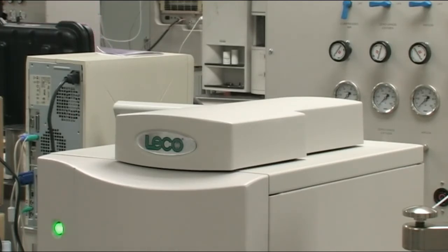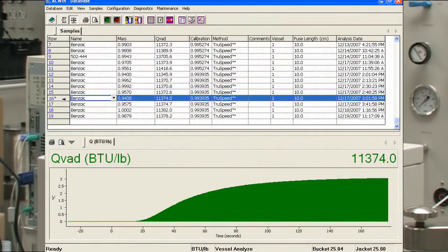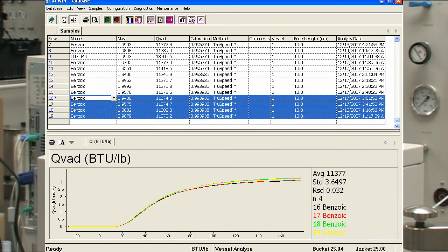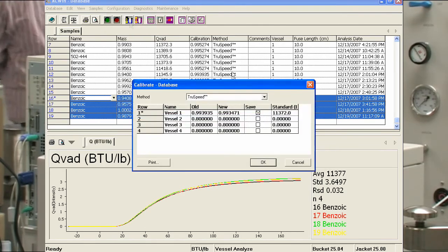What you'd like to do under standard operating conditions is run several benzoic acids, calibrate the unit, then proceed to run your samples. Approximately every 10 to 15 samples you may want to run a benzoic acid to make sure that everything is running correctly as a quality check. After your several benzoic acid samples have completed running, you want to calibrate the instrument. What you do is select the samples you want to use, go to calibration, and highlight calibration. This now calibrates the instrument. So you're ready to run your sample analysis.